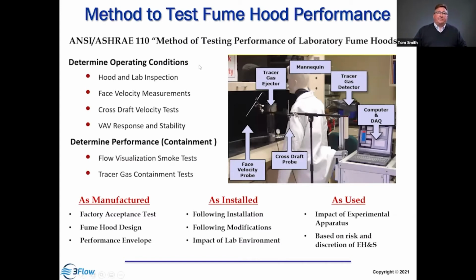So we measure the conditions under which the hood is operating. First and foremost, we're going to look at the hood and the lab and make sure it's properly installed. And then we're going to measure face velocity with a face velocity probe. We're going to measure the cross drafts in the lab, and then evaluate how the VAV system, the variable air volume system, modulates flow. If a hood is so equipped, we anticipate it's going to modulate flow in response to sash movement or occupancy, and we want to make sure that it does in fact modulate flow effectively.